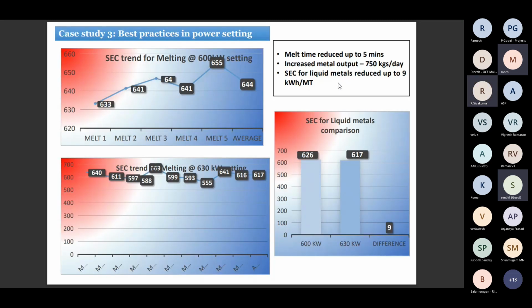Case study, power setting. One of the foundries had a problem with the maximum demand. They have a sanctioned demand of somewhere around 1150 kVA. The furnace capacity is 750 kilowatt, but due to the demand rising, they had to pay an extra penalty to the EB. That's why the foundry was using the power at 600 kilowatt. So we suggested studying the entire auxiliary loads and mains for 1 or 2 days. We suggested increasing by another 50 kilowatt, but on the safer side, the foundry set it from 600 to 630 kilowatt. 30 kilowatt additional power has to be given to the furnace area.